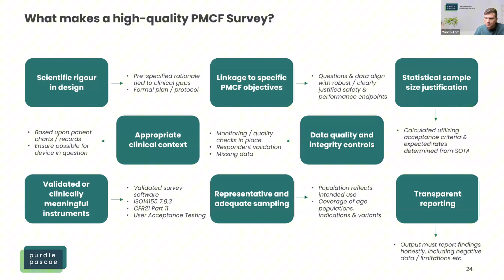Representative and adequate sampling. Make sure your population reflects the intended use. Also coverage of age populations. If you state that your device can be used for the pediatric population and neonates, do you have data that can feed back to that? And you might have different variants or sizes, so make sure you've got data across all of those. And then finally, transparent reporting. Your output must report findings honestly, include negative data, and include the limitations or any deviations from the protocol as well.